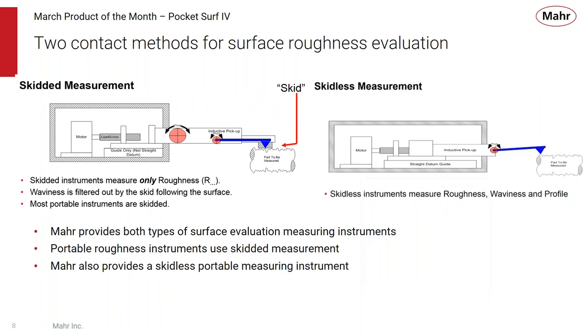But most surface finish measurements are done with contact methods, and the most common one is the skidded measurement system, where you can see here we have a probe that's driven by a drive unit. That probe has a skid on it, and the skid rides on the surface of the part, and a small probe contact protrudes through the skid to actually measure the roughness characteristics of the part. So this type of system only measures roughness. The waviness and the other profile information is all taken out because the skid filters that out.